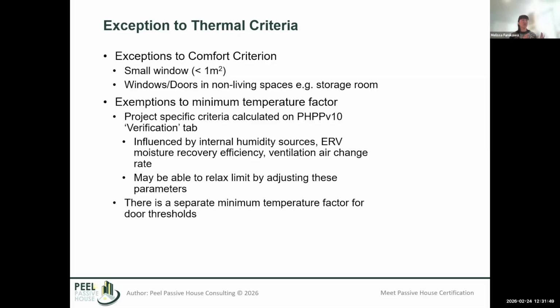Also, in terms of the fRsi temperature in the new PHPP, it used to be that the fRsi was related to what climate zone you're in, and it was a fixed value. Now, in the background, PHPP 10 calculates a project-specific fRsi, and it takes into consideration internal humidity sources, the moisture recovery from your ERV, and how much ventilation air change you have, because that all affects how much moisture is in the air in the building. That affects whether there's going to be condensation on a surface. And there's also a separate temperature factor for door thresholds.